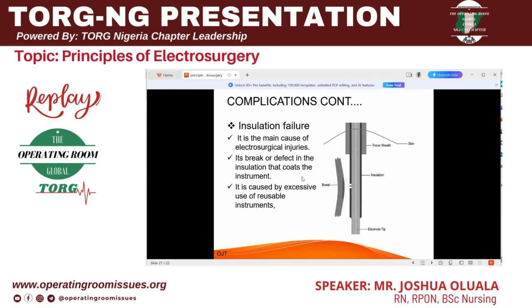Then another is insulation failure. We can see from the picture that the integrity of the insulation is not there; there is a break in insulation. Most of the time it happens with excessive usage of instruments, even though many of them are reusable. Of course, we need to be very careful with them. And how do we get careful with them? By careful inspection. We need to let the CSSD know they need to inspect these instruments for integrity, because if it's not there, the risk is very, very high of getting the patient's structure burnt.